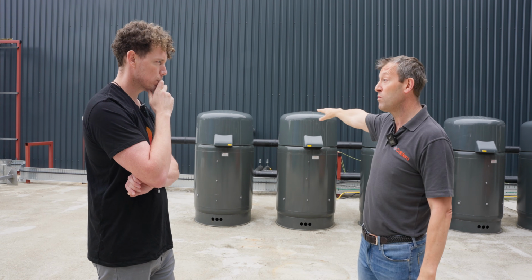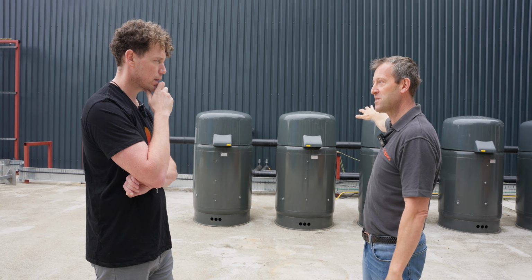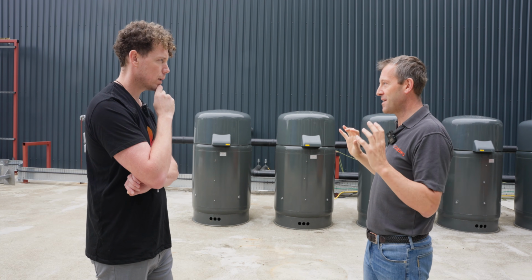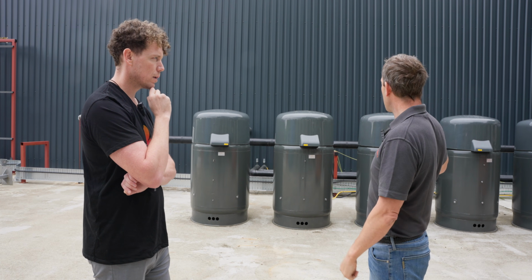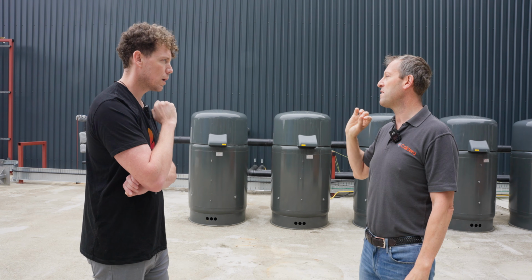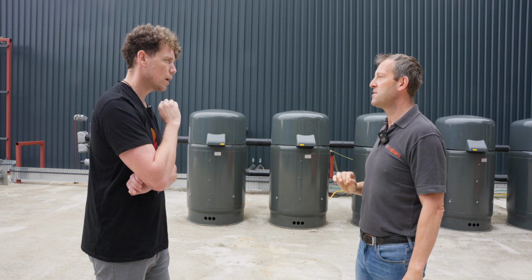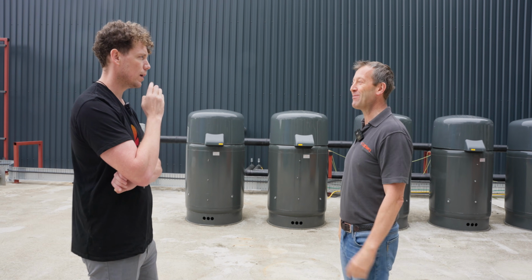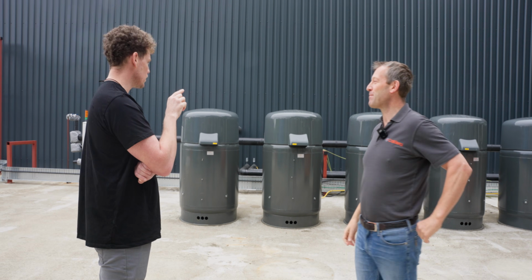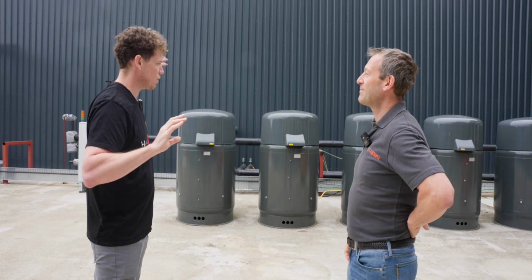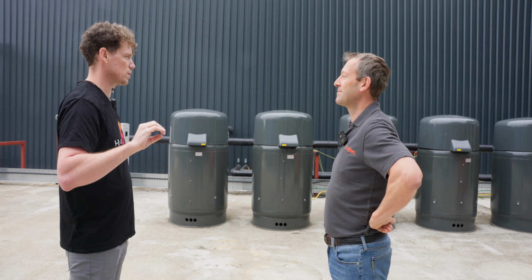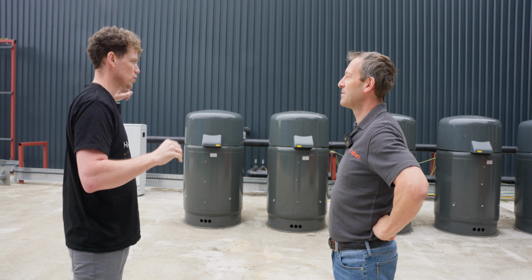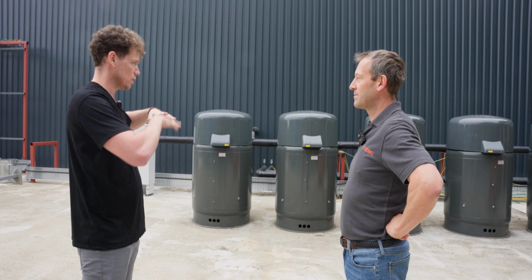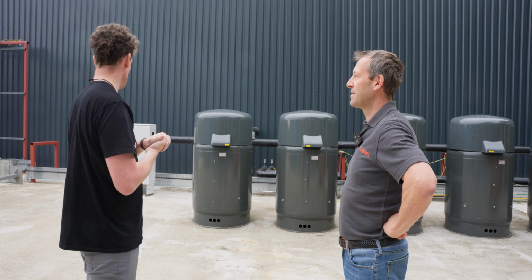These are relatively small, like a ton an hour of steam, though you might have 10 or 20 tons an hour elsewhere. This is why people use steam, and we're focused on it because it's actually quite hard to decarbonize with heat pumps. Your hospitals make a lot of sense here, since you're taking heat directly to point of use, you haven't got those Legionella issues, and you can just turn it off when you don't need it, so you don't emit the heat. Plus the smaller pipe work all makes a lot of sense.